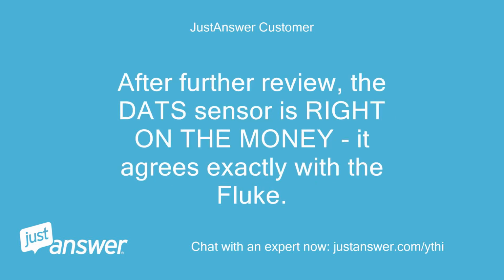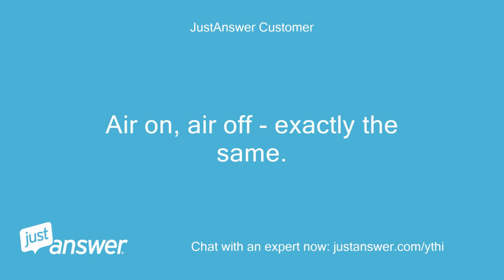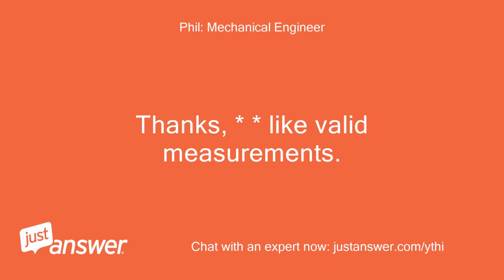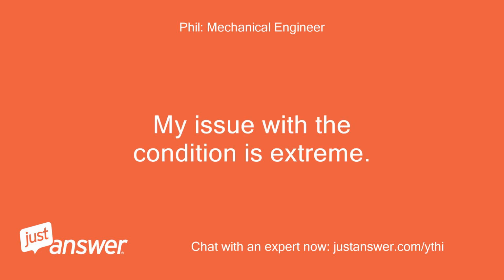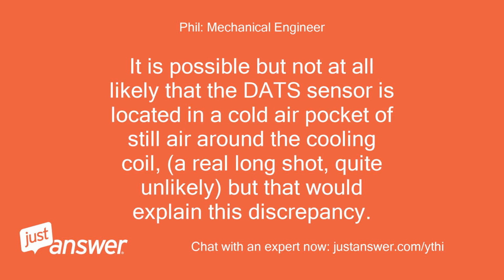After further review, the DATS sensor is right on the money, it agrees exactly with the Fluke. There is no error between the two readings. Air on, air off, exactly the same. Thanks, I like valid measurements. My issue with the condition is extreme. There is no way you could measure 55 to 57F on the diffuser outlets, that is right on the money correct, and 40-43F at the air coming off of the coil. It is possible but not at all likely that the DATS sensor is located in a cold air pocket of still air around the cooling coil, a real long shot, quite unlikely, but that would explain this discrepancy.